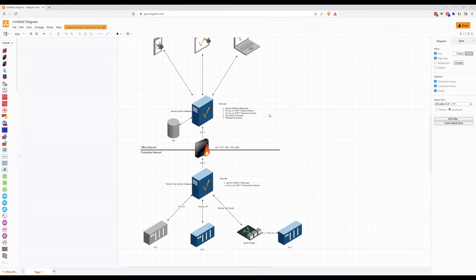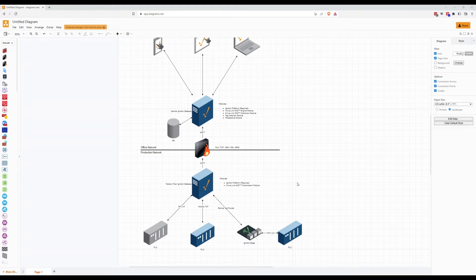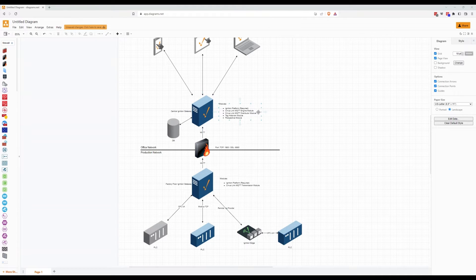For those not familiar with the Cirrus Link MQTT modules for Ignition: the Transmission module converts standard tags — reference tags, MQTT, OPC UA tags, OPC tags, memory tags, and so on — into MQTT tags that are then published over MQTT to the broker, which is the Cirrus Link MQTT Distributor module residing inside the central Ignition gateway. The MQTT Engine module is then used to actually read those tags from the broker.